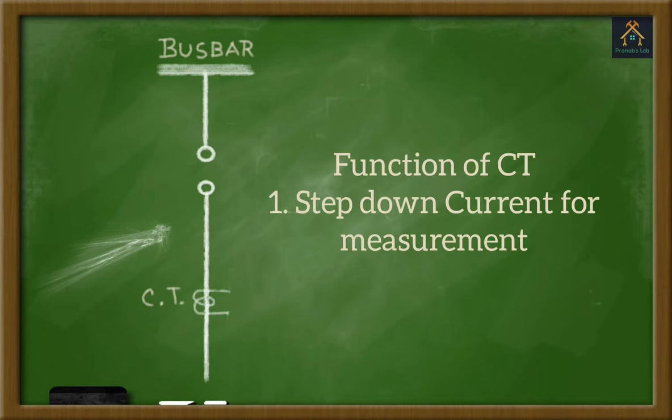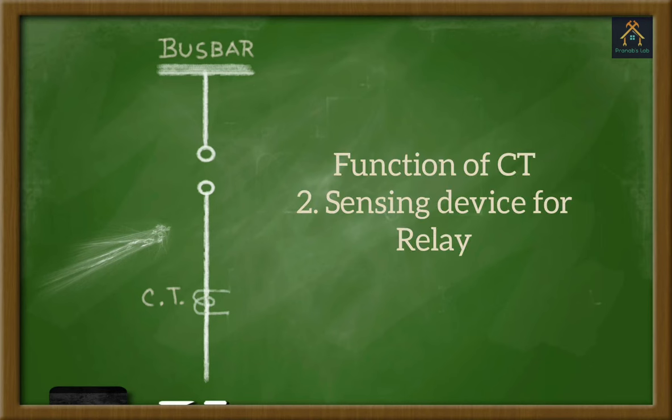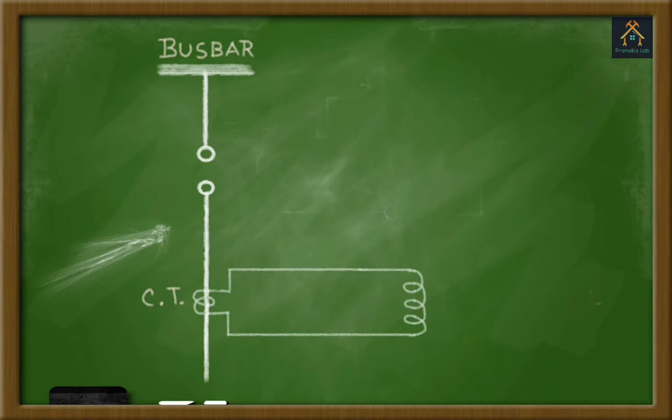Now, a CT that means current transformer is placed in that line. Basically, a CT is used to perform two basic functions. Firstly, to step down the current and measure the line current at a certain ratio and secondly, it works as a sensing element of a relay. In the figure, you can see the CT secondary terminals are connected with a relay coil.